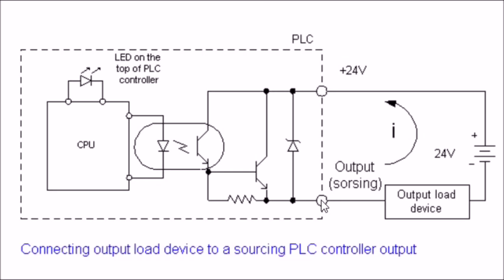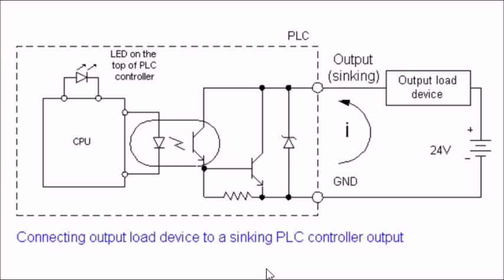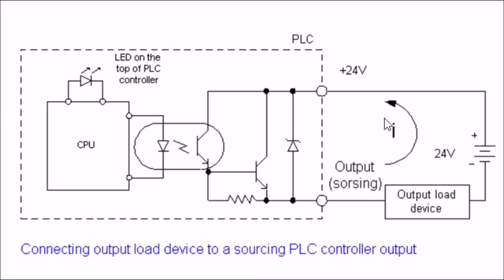Again, we have the same output circuit. I didn't misspell that. The manual did. In this case, the load is connected in the negative side. Of course, the negative side of the circuit still has to go to the emitter side of the transistor. And the positive connects directly to the collector of the power transistor optocoupler assembly. When it switches on, we're going to source the current through the transistors to the device. So, again, this is why you have to understand you can place this load either in the sourcing configuration or the sinking configuration. Works either way. Depends on the design of the device and how you want to place it. And you still need, if it's a DC device, you still need to observe the polarities of both the output circuit and the load itself.